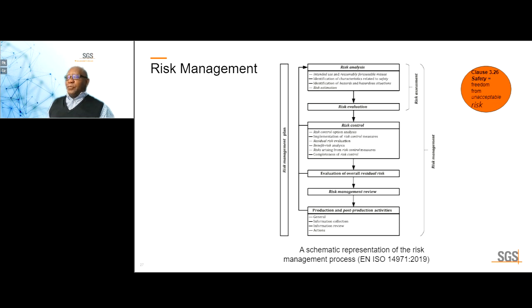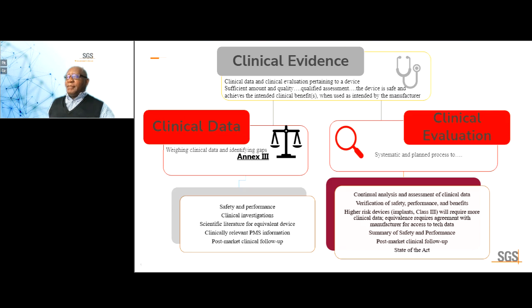The next big ticket item will be clinical evaluation. And I'll take this in steps. Going from the bottom of this slide up, I'm looking at clinical data. So you have to generate some clinical data. You could do that in one or a combination of several ways. You could do it through scientific literature for equivalent device, if that's what you wish to claim, bench testing, clinical investigation, or relevant clinical PMS information that you may have generated.